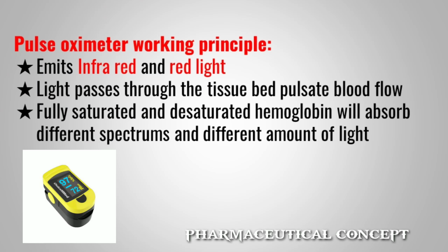Now we are going to discuss the pulse oximeter working principle. Generally, a pulse oximeter emits infrared and red light. Both lights pass through the tissue bed and pulsating blood flow. From that, fully saturated and desaturated hemoglobin absorb different amounts of light at different spectrums. Based on that, it calculates and gives you the percentage of oxygen present in the blood.